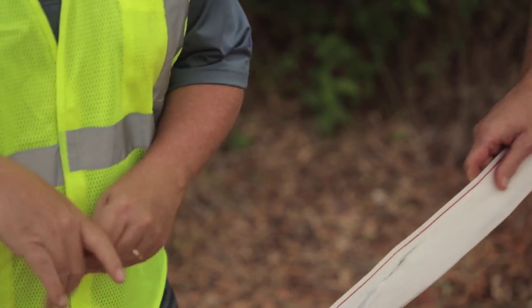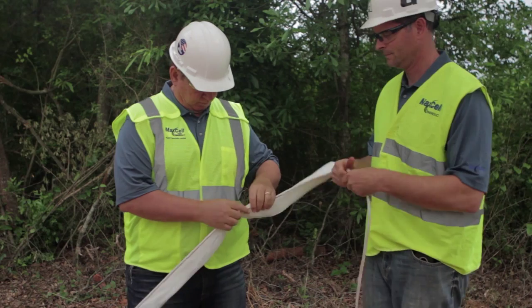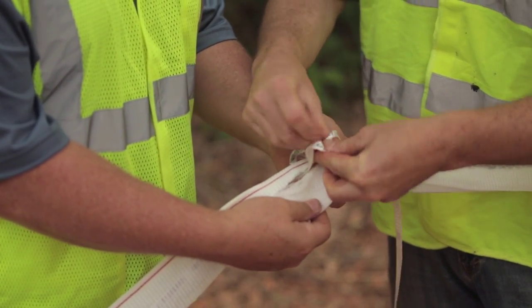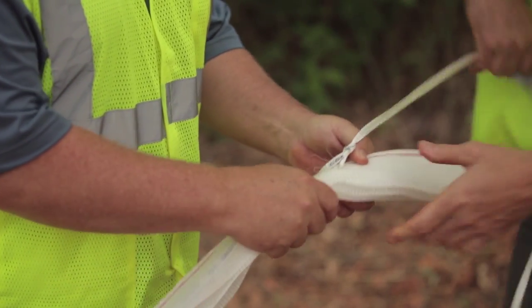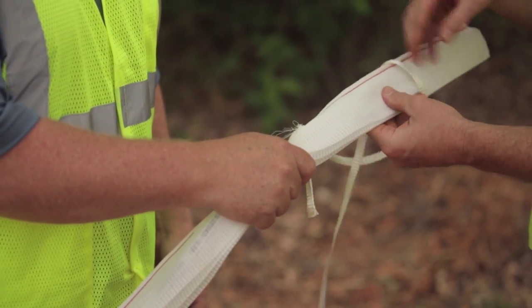Now that your pull tapes are cut back, this is how to make a MaxCell pulling harness with scrap pull tape or rope. First, tie the rope or tape to the slit area. Then make 4-5 half hitches to form your grip on the end of MaxCell.